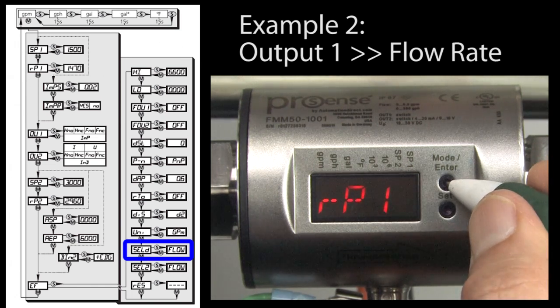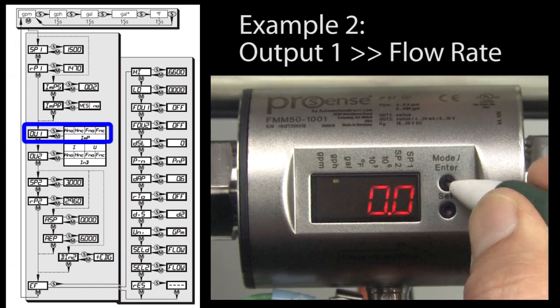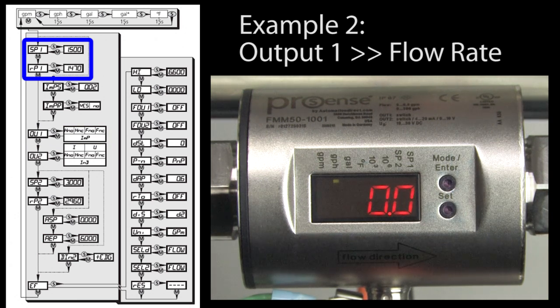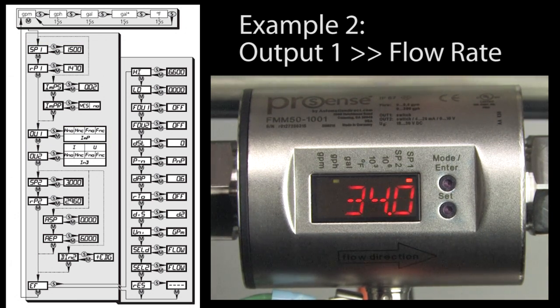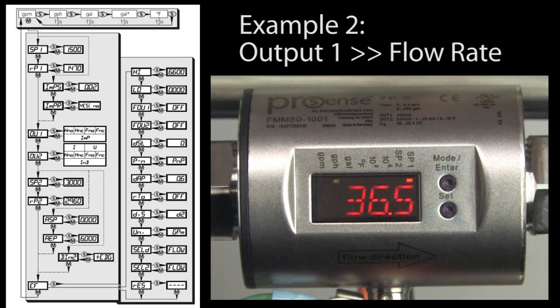That's it. Just select the output mode, how you want it to react and adjust the limits. If I turn the pump on, we see the flow rate is between 30 and 40 gallons per hour and output 1 is active. Perfect. If I modify the flow so it's outside my window, output 1 goes inactive. Exactly what we expect.